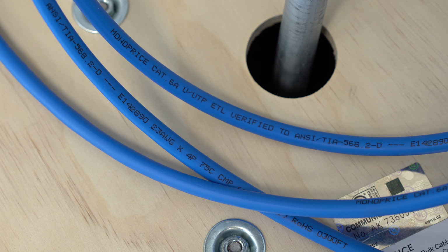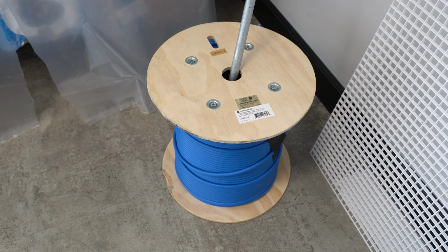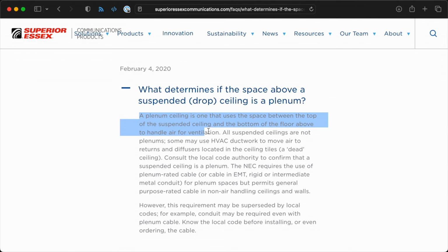Plenum cable has a jacket on it made of PVC or FEP, which are basically less flammable and emit less toxic fumes if they do catch fire. They're not fireproof, they're just doing a little extra to help reduce the loss of life in case of a fire by delaying its spread and reducing the number of harmful toxins. Not all ceiling spaces are plenums. There could be ducted returns. But my space is, so I have to use plenum-rated cables.